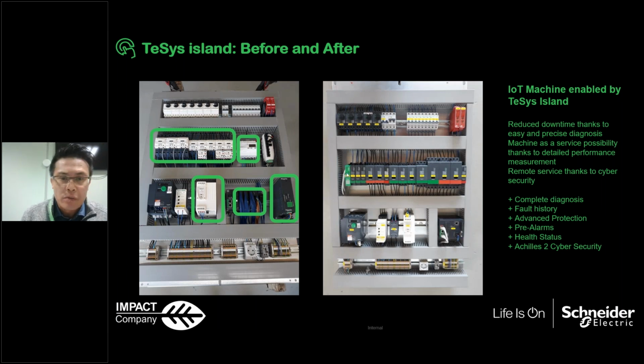And then to the PLC, it is very simple, just one Ethernet cable, and then you can communicate with the PLC system. Each TeSys Island will have a dedicated IP address. So the PLC simply accesses this IP address, and because this is a Modbus Ethernet protocol, the register is open. We have the register table for which data you would like to get from the TeSys Island to the PLC. So you just follow the register table, and then you can have all the data.